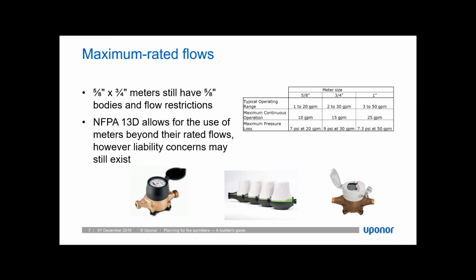I mentioned maximum rated flows, and the one thing that I want to point out from this slide is the difference between the maximum continuous operation flow that's allowed and the maximum allowed flow for intermittent usage. Continuous operation means 24 hours a day, 7 days a week, that it can flow and there would be no damage to the meter and no loss in metering capabilities. For a 3/4 inch meter, this is about 15 gallons per minute typically. And like I said, though, the typical operating range can go all the way up to 30 gallons per minute. So that is the maximum allowed flow of a standard 3/4 inch meter.